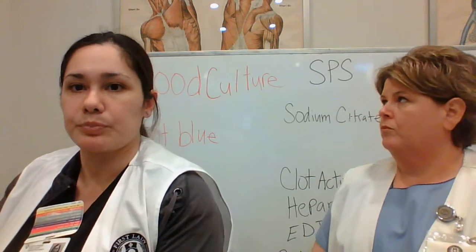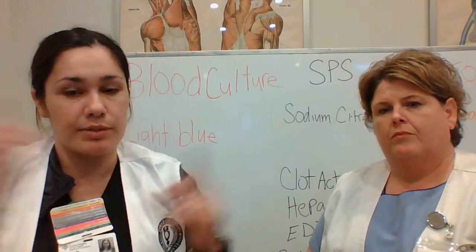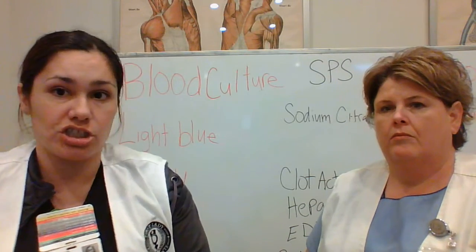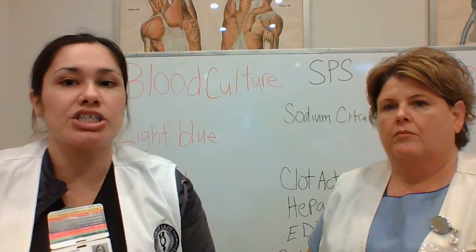Unidirectional means it goes from the analyzer to the computer, or bidirectional, which means it can go in both directions. CIC is Connectivity Industry Consortium, established to ensure that any POC analyzer can talk to any lab information system, allows the workers to transfer point-of-care test results into the patient's chart. Guidelines for standardization developed by manufacturers, LIS vendors, and healthcare providers.